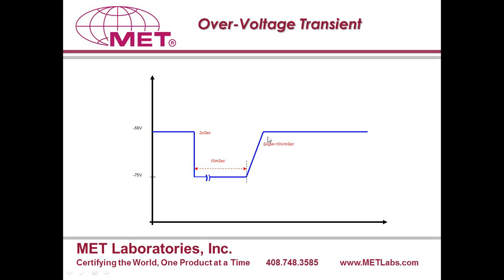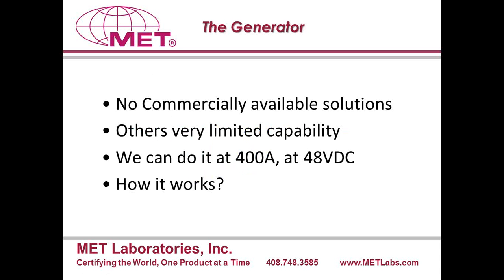However, the rising slope, if I could call it that, the way it's being shown on the screen, is 10 volts per millisecond, which is not that big a challenge. However, there are some technical difficulties which I will elaborate on in my next few slides. What are those difficulties? This waveform gets more complicated compared to the undervoltage, especially due to the fall time of 2 microseconds. What are the problems out there? What are the main concerns there?